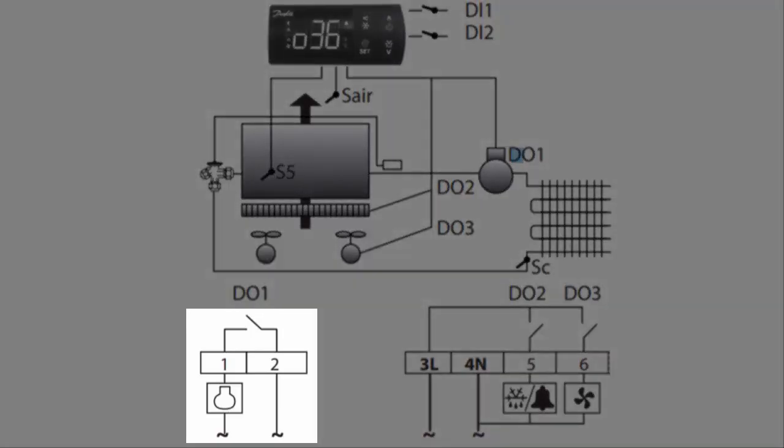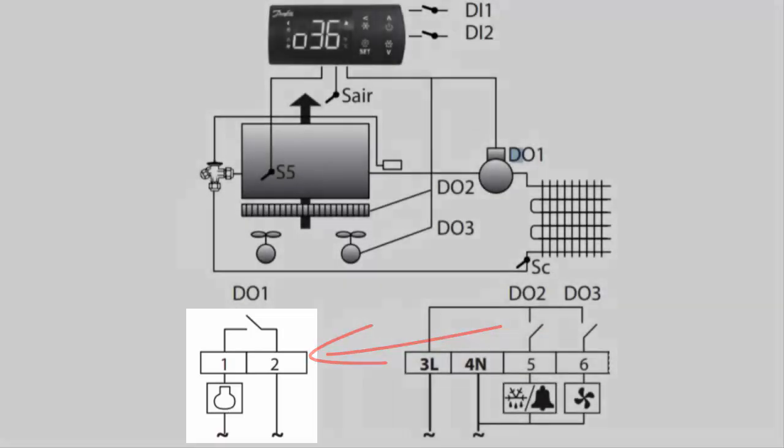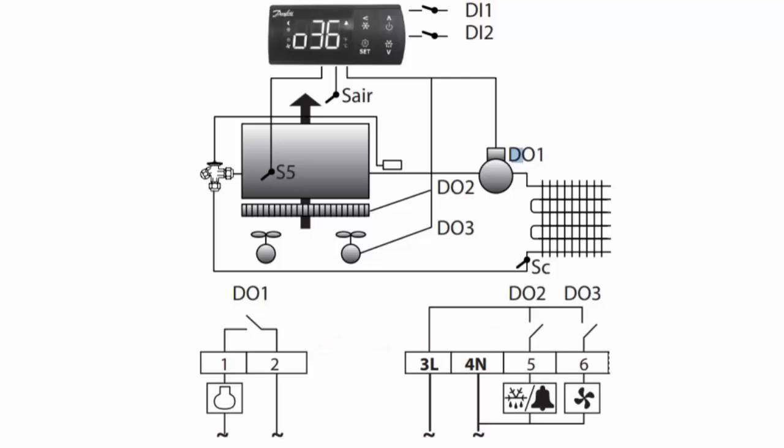This is a dry contact because there's no automatic input on the control for terminals one and two. To power the compressor, you have to apply power - 240 volts or 120 volts depending on the compressor. You apply power to terminal two and it goes out on terminal one, or vice versa. It's dry because it's not taking power intrinsic to the control.